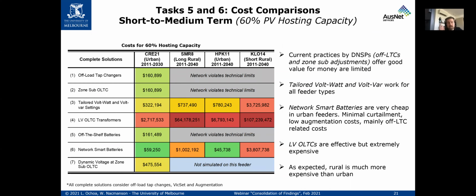What we can really highlight is that solutions 1 and 2, the traditional solutions, are very cheap, and that's why the DNSPs are doing that today. For the current hosting capacities we have, they're a very cost-effective solution. However, for CRE21 at 60% they work, but the other feeders start running into voltage problems, so you need to look elsewhere for these feeders, and certainly for higher PV penetrations.